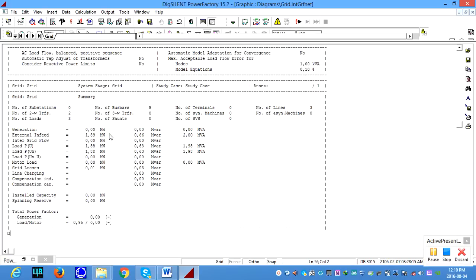You can see there is no generation because we never used any generators. It's only an external infeed. It is 1.89 megawatt, and also we have the loads, which is 1.88 megawatt as the real power and the reactive power of 0.63 megavar. And we can see the MVA capacities. The external grid is 2 MVA and the loads are trying to consume 1.98 MVA. Okay, and the loads are operating at 0.95 power factor.